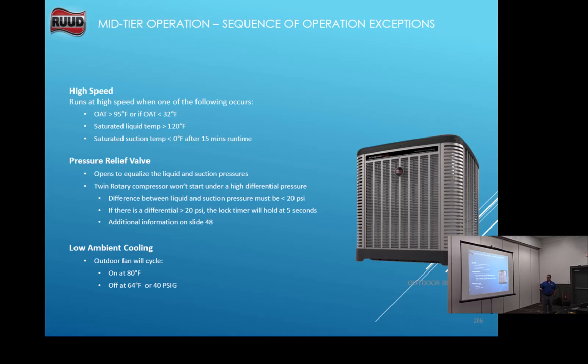The 15, 16, and 18s have low ambient cooling. So I know some of you guys work in the school district here, so you got a lot of heat load inside, so this is going to work. Outdoor fan will cycle on at 80, off at 64 or 40 psi. So if you're checking pressures on it or something, just be aware it's going to act just like a fan cycle switch on and off in low ambient cooling condition.